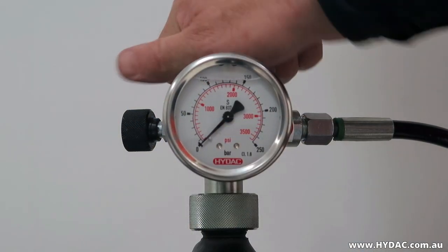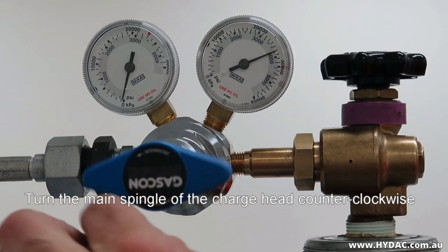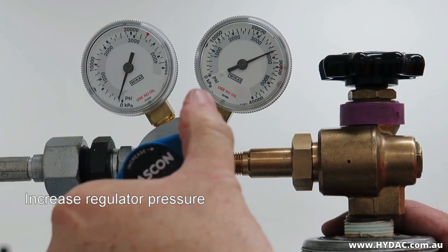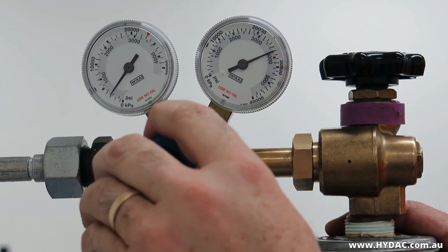Slowly turn the main spindle of the charge head counter-clockwise about three turns. Begin the gas flow from the bottle to the accumulator by slowly raising the pressure at the regulator. When shipped, the majority of HYDAC diaphragm accumulators are charged to two bar.